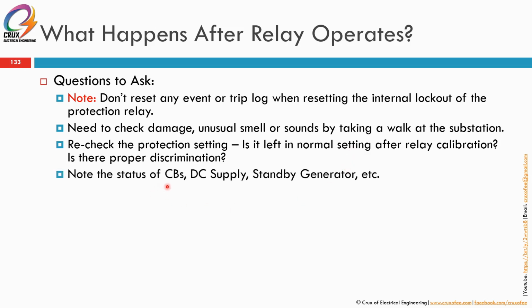Number 3, note the status of the circuit breaker, DC supply, and standby generator. So you also need to look at the status of the circuit breaker, and whether the DC supply was lost. But in most of our systems, we are using shunt trip, which means the DC supply is only used when tripping. But some systems use a fail-safe type, which means that the DC supply must always be on. If the DC supply fails, then the relay will trip. So these are the other external causes that can cause your relay and breaker to trip. Then note whether any standby generator kicked in.